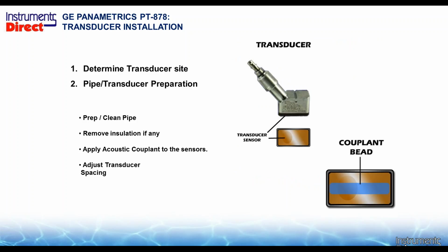And installing the transducer on the outside of the pipe. I'll tell you, things have really changed on this side of the fence here on installation. In days of yore, people would come out with a grinder and a wire brush and sandpaper and all kinds of things to prep the pipe. Not necessary anymore. The rule of thumb is remove insulation from the pipe. Don't cut little cookie cutter holes. Remove a line and a complete circumference of insulation on the pipe. If something is loose on the pipe, a rag or a wire brush is all you need. You do not need to take the paint off.